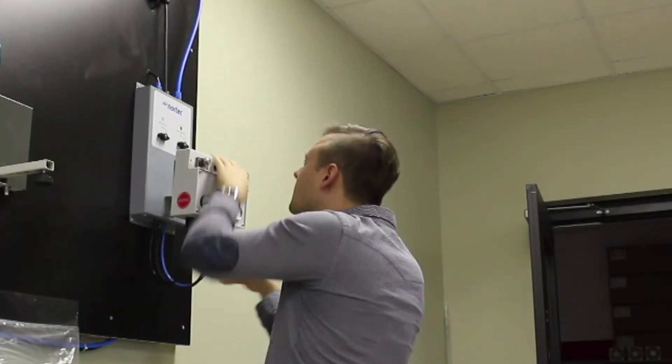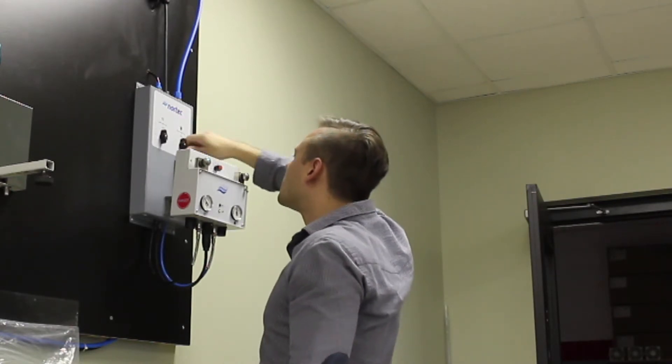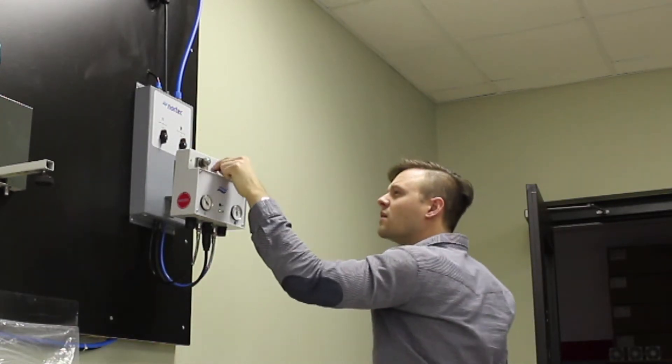Electrical is supplied from a 120-volt line and is stepped down to 48 volts via a transformer that is capable of supplying up to 4 units. The AF22 creates and maintains precise relative humidity levels and is capable of supplying up to 22 pounds of water per hour.